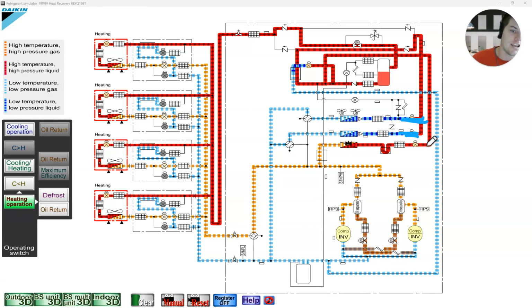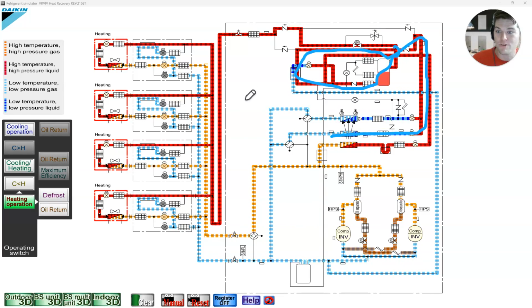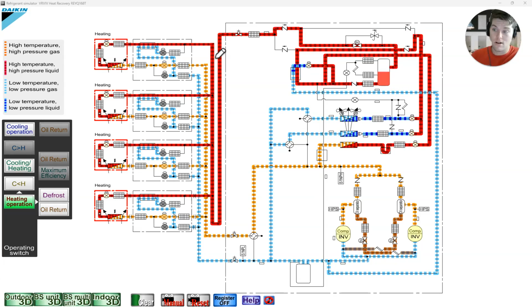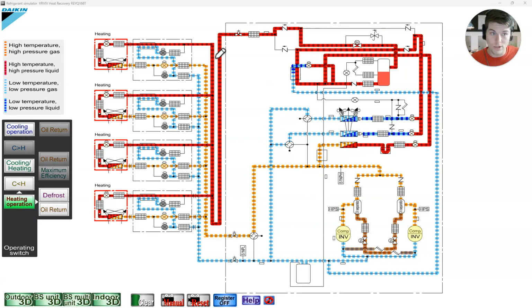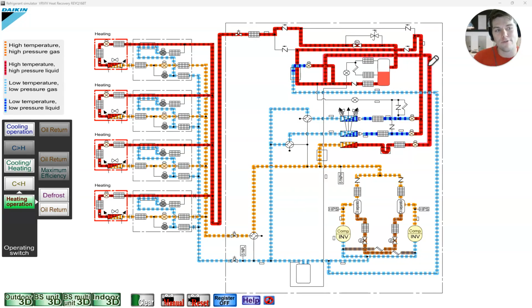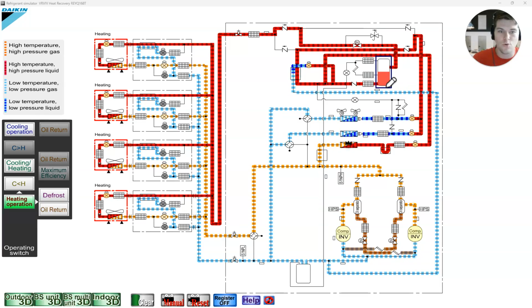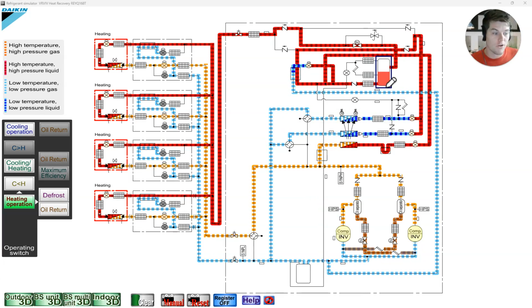It stays in this state long enough and we lose control, and this now becomes a low pressure line back to my liquid receiver because again, we're not making any liquid, guys. That's what's happening. And you're going to find this on a lot of systems that are low in charge in heating mode when it's cold outside, that this line actually turns into a suction line if there's not enough refrigerant to push through it. Liquid receivers do what? They stack liquid.